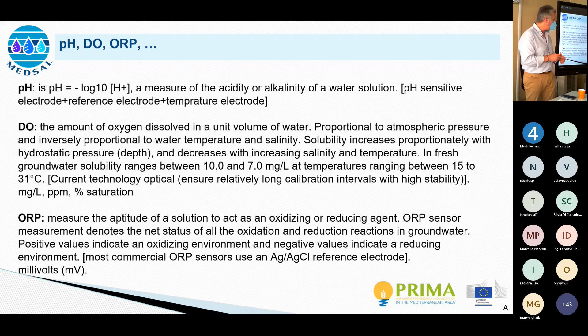Now, the important thing about the ORP electrodes is that they're very, very sensitive. Overall, it's a very, very difficult measurement, and you need to be aware that the level of stability, the time of stability, is very, very low. So you're looking at calibration intervals that, as a practical rule of thumb, would not extend more than 1 month in the best case. So you're talking about a difficult measurement which has a lot of drifting and needs to be repeated pretty often. Next one, please, Vasilis.